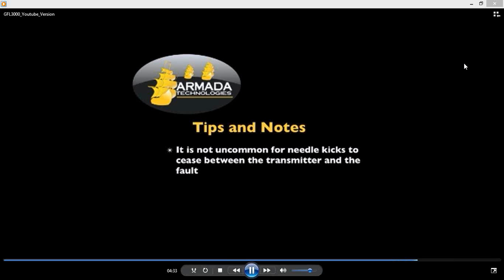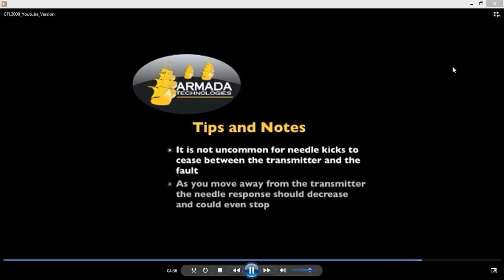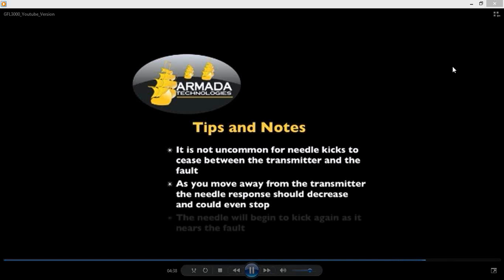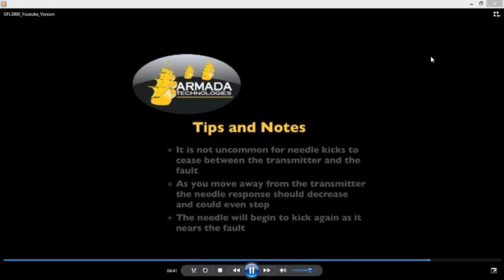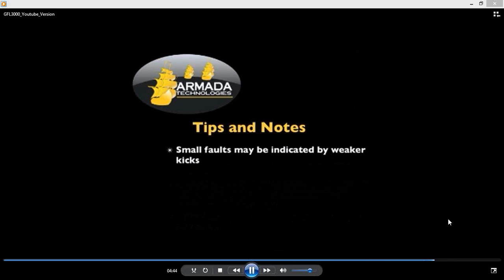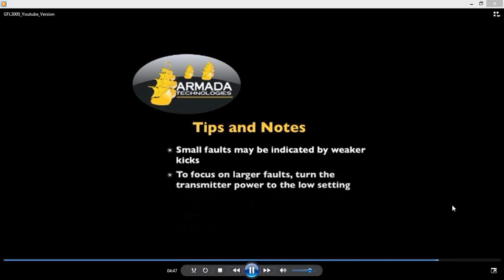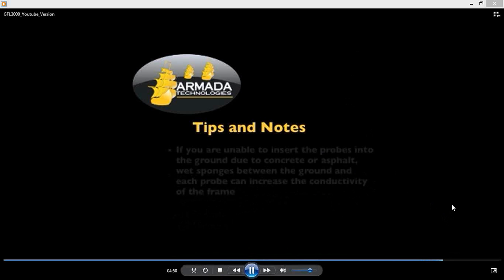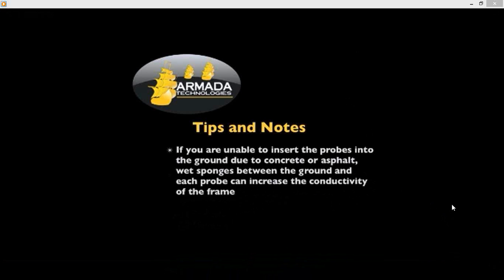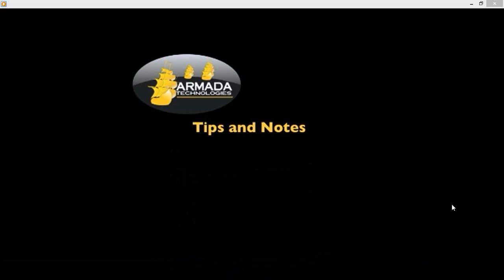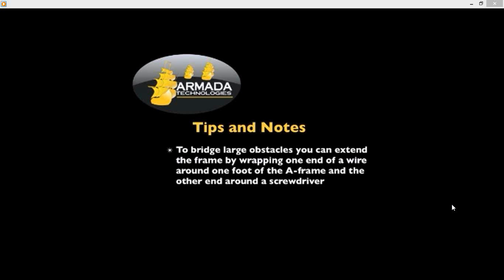It is not uncommon for needle kicks to cease between the transmitter and the fault. As you move away from the transmitter, the needle response should decrease and could eventually stop. The needle will begin to kick again as it nears the fault. Small faults may be indicated by weaker kicks. To focus on larger faults, turn the transmitter power to the low setting. If you are unable to insert the probes into the ground due to concrete or asphalt, wet sponges between the ground and each probe can increase the conductivity of the frame. To bridge large obstacles, you can extend the frame by wrapping one end of wire around 1 foot of the A-frame and the other end around the screwdriver. Then use the screwdriver as you would the second probe.